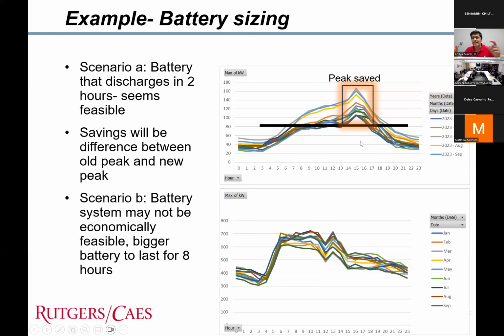So I want 80 kilowatts to last for 2 hours, so I would have a 160 kilowatt hour battery. I would multiply that with the implementation rate per kilowatt hour, which is in the next slide, to get an implementation cost. This is a very quick, fast calculation you can do. The implementation cost I have here is around $500 per kilowatt hour.